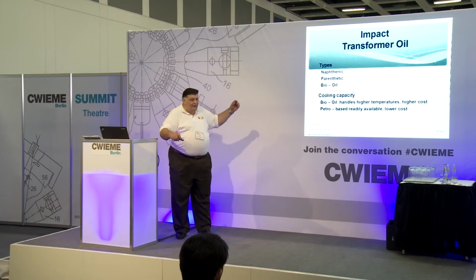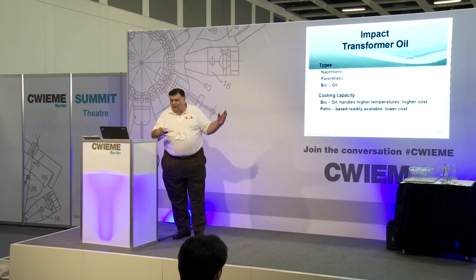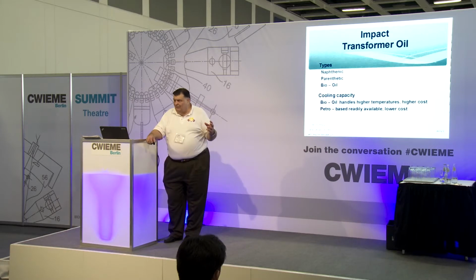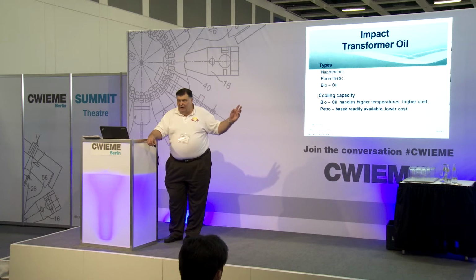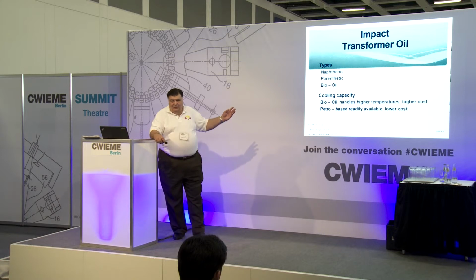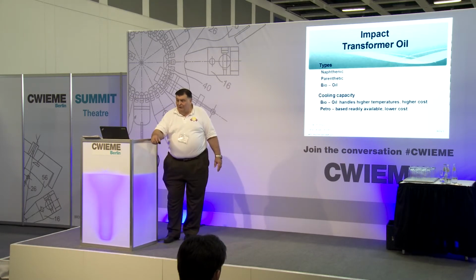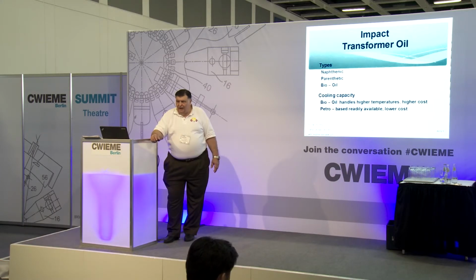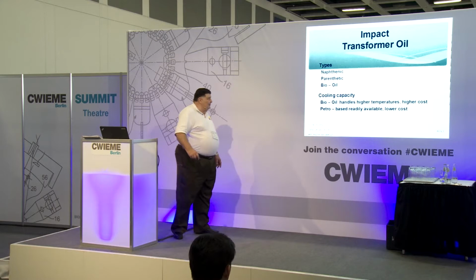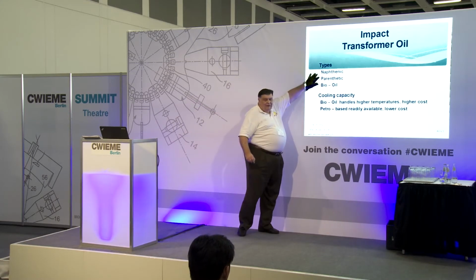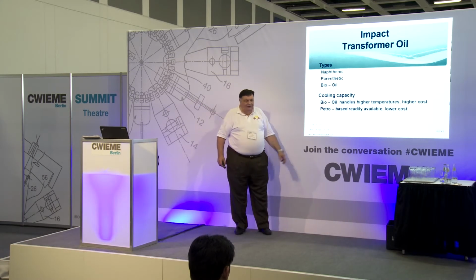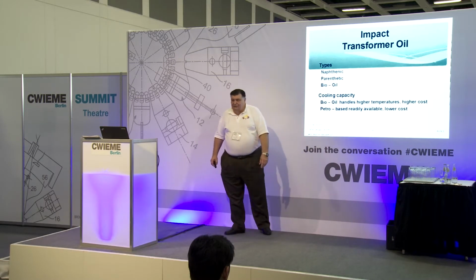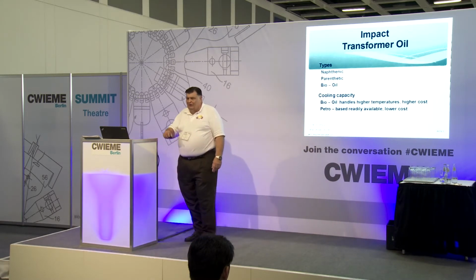If you can go to some of the better electrical steels and use aluminum in both windings, or you go to amorphous and use aluminum in both windings, your operating temperature is lower. At that point, you can keep your transformer almost the same size, and you may not need to add additional oil. Higher operating temperatures: these two have a limit. The bio-oils could be operated at 50% higher temperatures.